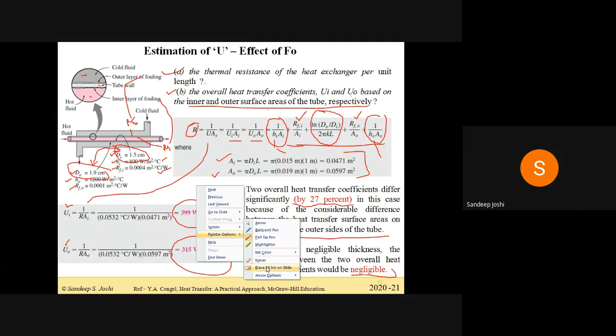For tubes with negligible thickness, the difference between the two overall heat transfer coefficients would be negligible. That's why in actual practice we take very thin tubes, but there are certain practical limitations to going with a thin tube, because a thin tube will corrode early, and it may reduce the life of the heat exchanger. That's why it depends on the application, what the two different fluids are, and what their corrosiveness is. So a compatible thickness and compatible tube material is generally chosen for the different applications of heat exchangers.